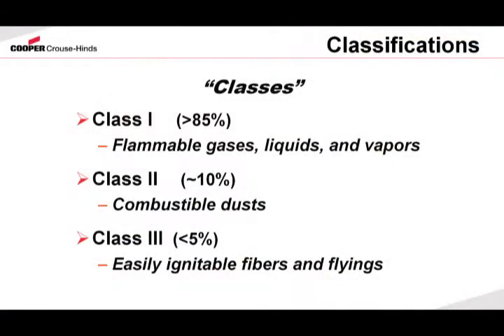The building blocks for hazardous locations are classes, divisions, and groups. When we're talking about the classification of the product, we're talking about whether it's a gas, vapor, or liquid for Class 1. For Class 2 locations, we're dealing with combustible dusts, and in Class 3 locations, we're dealing with flyings and fibers.